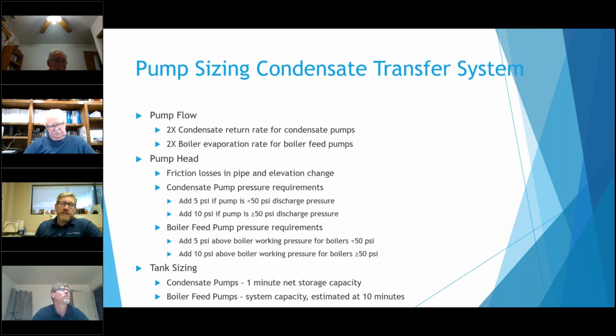The tank size that's on these, kind of maybe cut off on the bottom there a little bit, but for the condensate, basically those pumps are designed to run for 1 minute. You want to get the condensate out of there as quick as possible. You don't want to let it cool down or anything like that, so you're not reheating it back up in your boiler feed unit or your deaerator. So it's not really going to stay there too long.